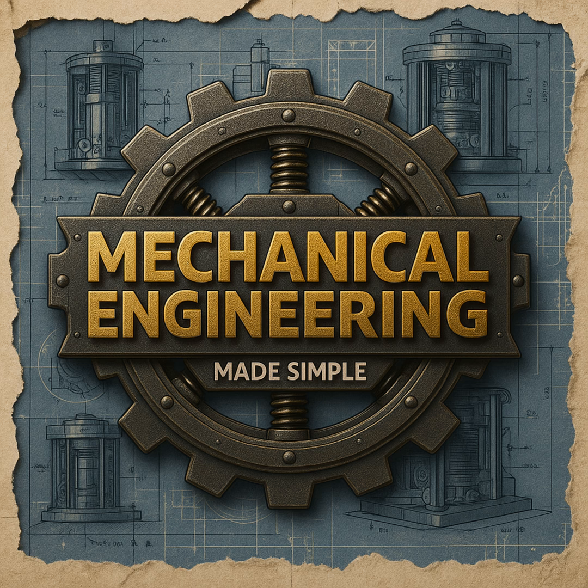And the design of heat exchangers becomes life or death here. Absolutely. In a power plant, if your heat exchanger is a bit inefficient, maybe you have a 5-degree difference instead of 2 degrees, you lose 1% of fuel efficiency. No big deal. In cryogenics, because the temperature difference delta T represents such a huge loss of exergy at low temperatures, a slightly inefficient heat exchanger can completely stop the machine from working. If the incoming gas isn't pre-cooled perfectly by the outgoing gas, the cycle fails. The exergy loss is magnified at low temperatures.